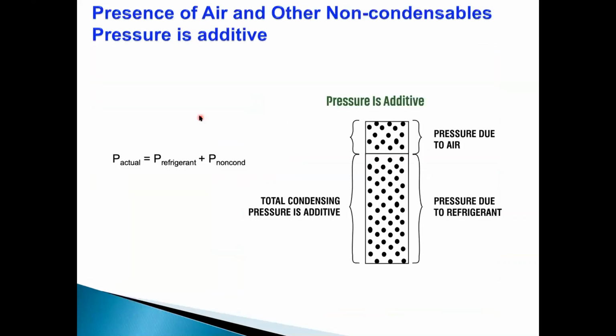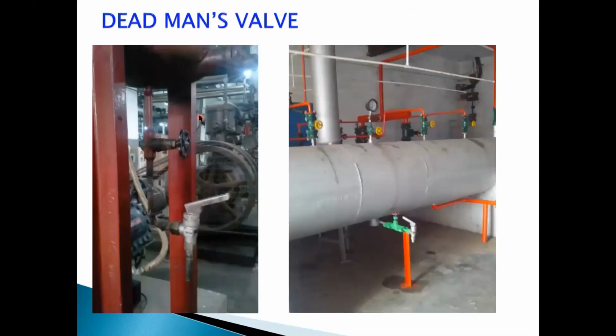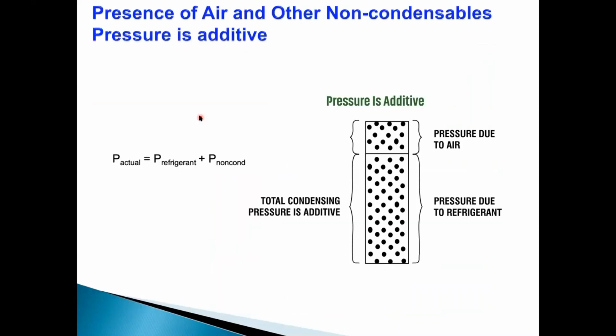Let's talk about other important energy saving and safety equipment. I'll try to go through that because we have limited time. Air and water are the two important things which affect the performance of any refrigerant system, not only ammonia. Why? Because pressure is additive.